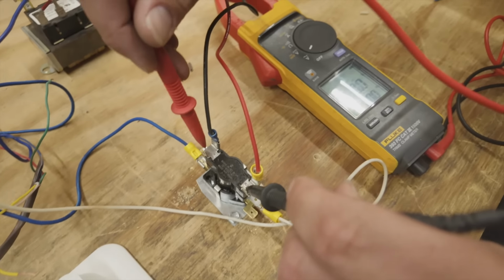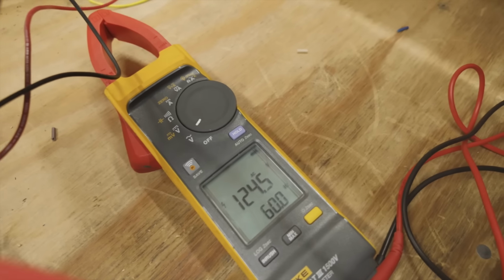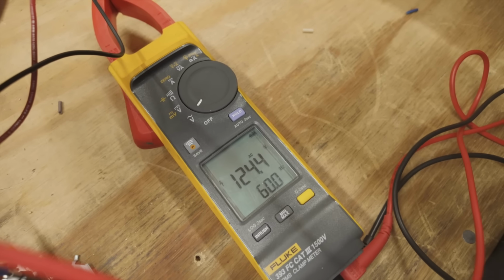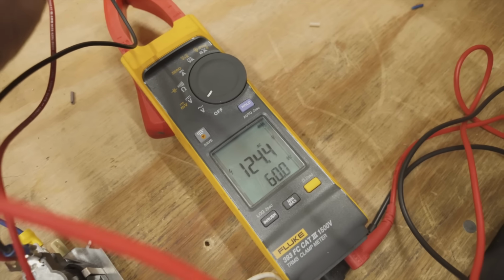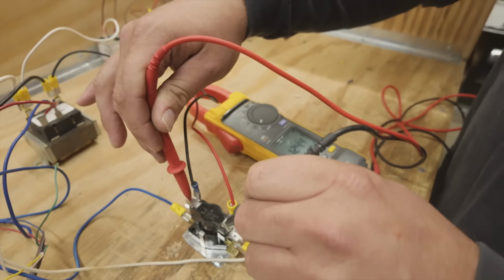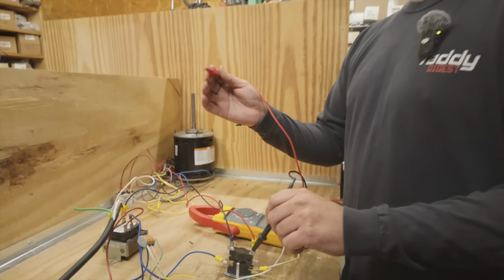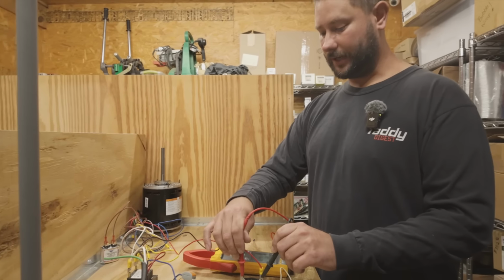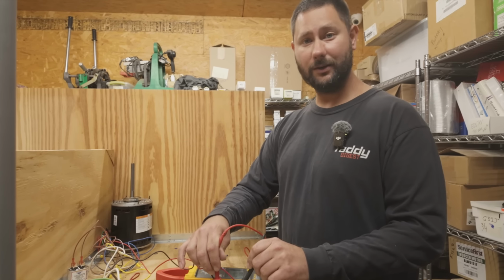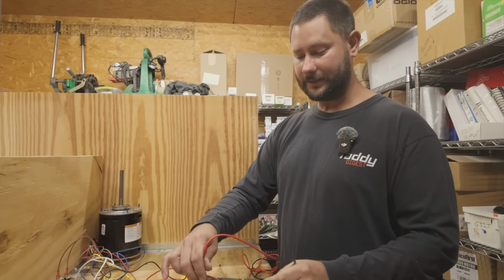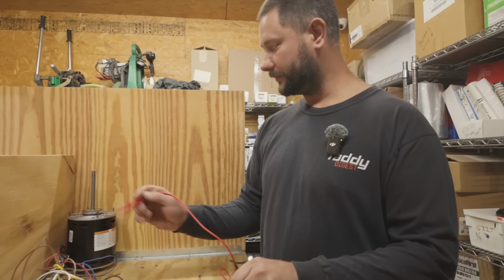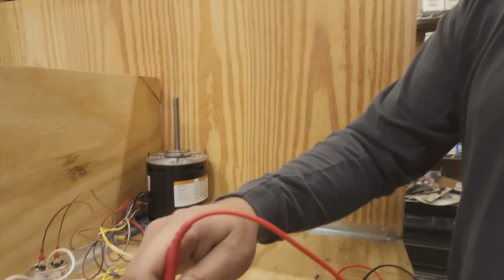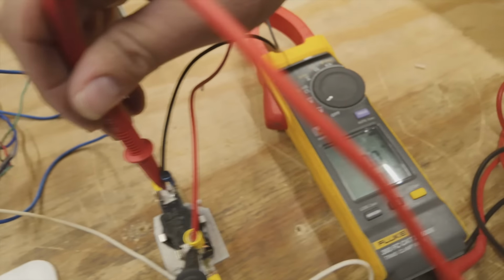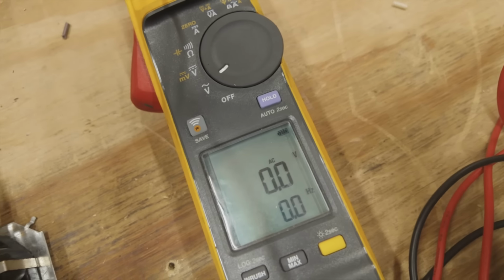But is this closed? No, it's not closed. Why? Because it's got a delay. Sequencers have a delay. What's going to happen though? Once it finally closes, we're not going to read 124, we're going to read 0. From white to this side, we're going to read 124. Look, fan motor's running. We're reading what? 0, right? We completed the circuit.